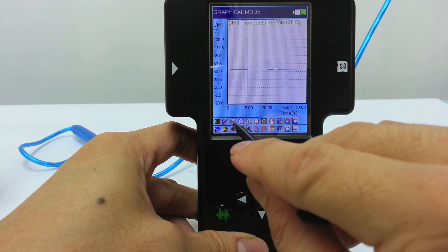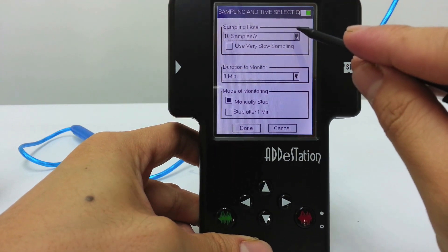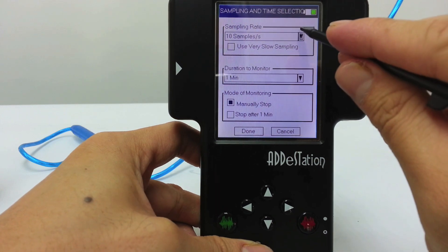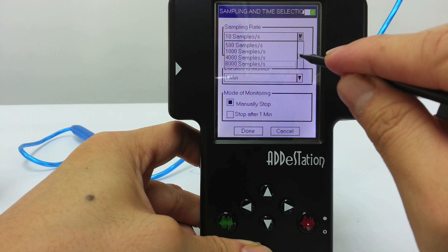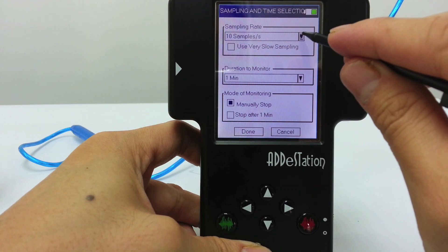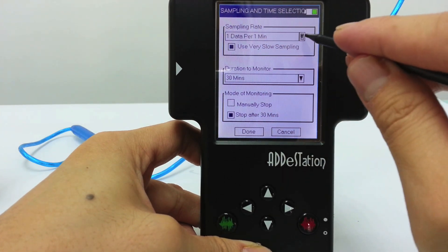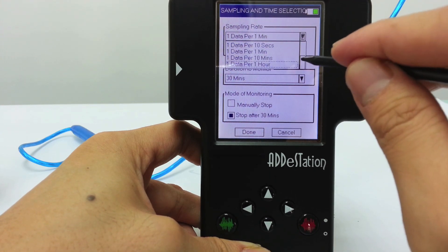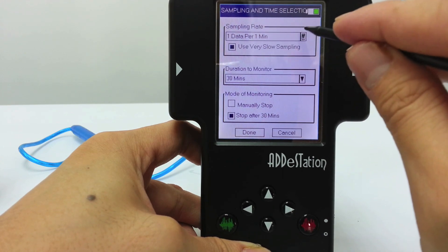Let's look at what this does. This button over here — the third button from the left, which shows a little clock — is the settings for your sampling. You can choose to change the sampling rate. You can have a range between one sample per second to 32,000 samples per second, which is pretty high. Or you could opt for very slow sampling — collecting one data point per minute, per hour, per 10 minutes, and so on. That's really up to you and depends on the situation.